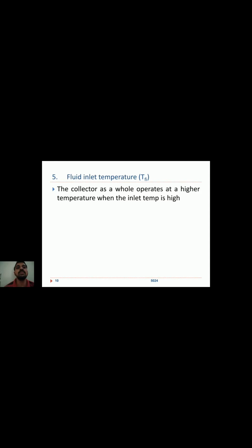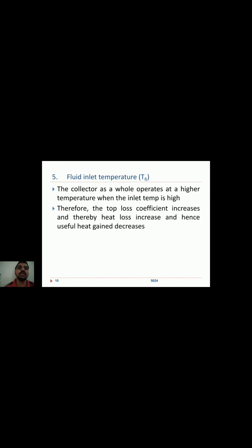When the inlet temperature is high, the collector will be operating at a very high temperature, and the temperature difference between the collector and the ambient will be high. The top loss coefficient increases. If the top loss coefficient increases, what will happen? The heat loss also will increase, and hence the useful heat gained will decrease.